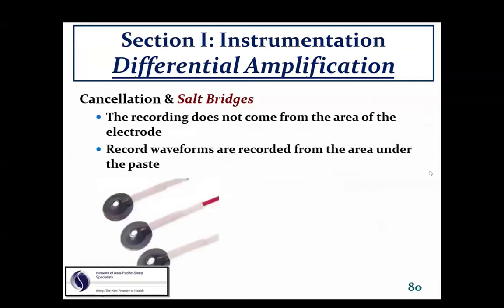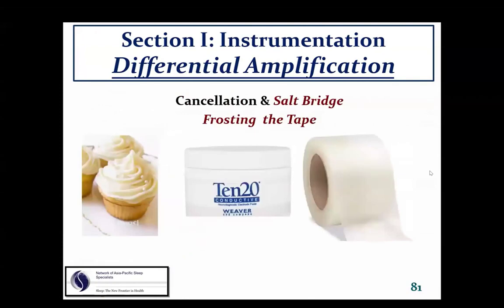So the data we're recording does not come from the area of the electrode. The recorded waveforms are recorded from the area under the paste. So if you have more paste on the edges of the electrode, that's your surface recording area. I did a training 2 years ago, and they had called because they couldn't understand why their EEG waveforms didn't look like they did in the textbooks. And I checked everything. They had the appropriate sensitivity. They had the appropriate impedance validation. I couldn't figure out how this possibly could be true. And it was happening on every patient.